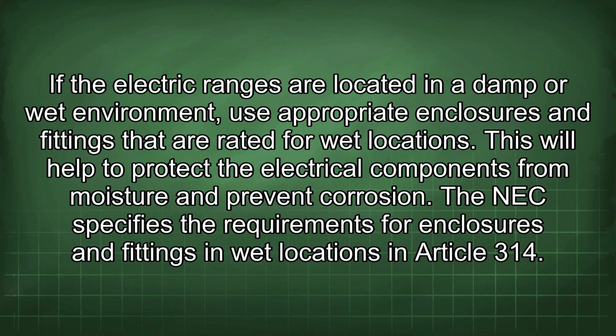If the electric ranges are located in a damp or wet environment, use appropriate enclosures and fittings that are rated for wet locations. This will help to protect the electrical components from moisture and prevent corrosion. The NEC specifies the requirements for enclosures and fittings in wet locations in Article 314.